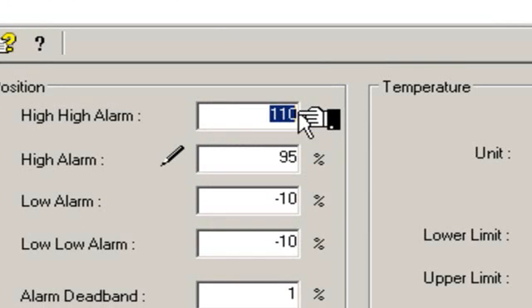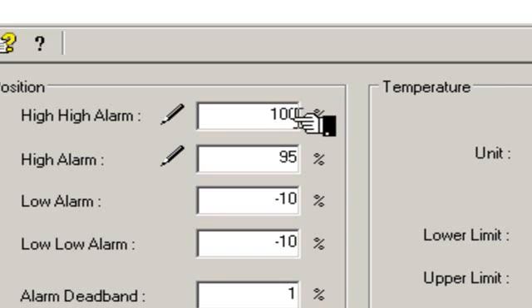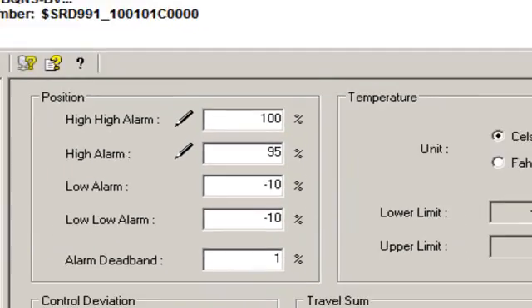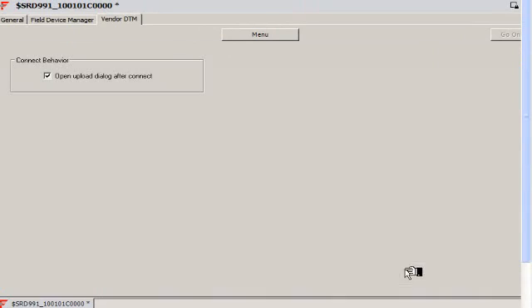Let's just say we want to make that high alarm 95%. Let's say we want to make the high-high alarm 100%. Now we've done that. We've clicked Apply, and we've clicked OK.